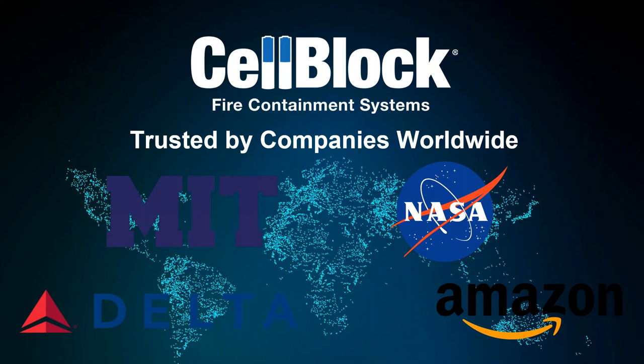Yeah, it does. Thank you. And further along the lines of the drums and even the boxes, can the drums or boxes be reused after they've been used? Yeah, we get that question a lot. So absolutely, because back to how I discussed earlier on the cabinets, if you had an incident on shelf two, you're not going to lose anything on shelf one and shelf three. The fire containment tiles and panels are specific to a shelf. So if you have an incident and there's a thermal runaway on shelf two, we lose all the batteries, the whole thing goes up, but everything's going to be contained to that.